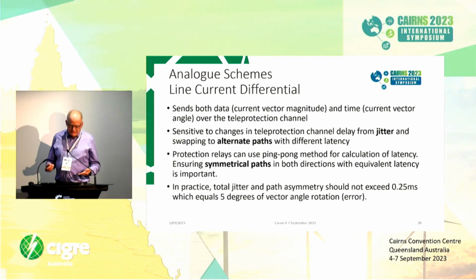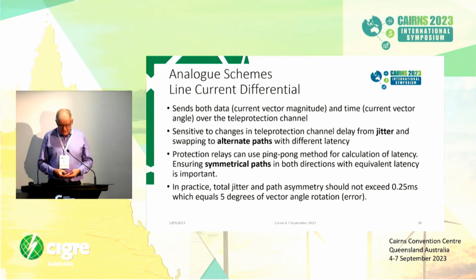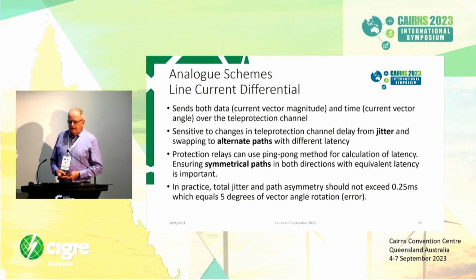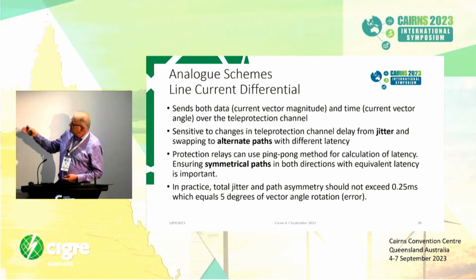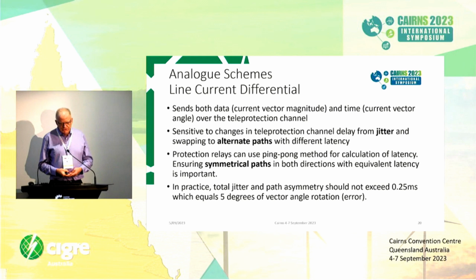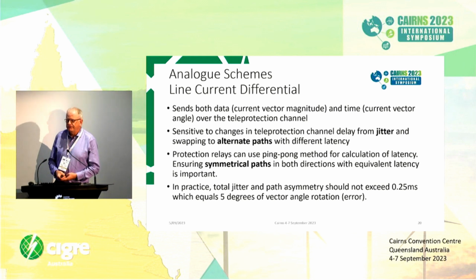And in practice, the guidance I try to stick with is that total jitter and path asymmetry should not exceed 0.25 of a millisecond, which equals about 5 degrees of vector angle rotation in the system. That's just guidance. Obviously if you're using precision time protocol or PTP, you can far exceed that, but if you're using the ping pong method, 0.25 milliseconds is what I've found is the maximum you should permit with your latency and jitter.